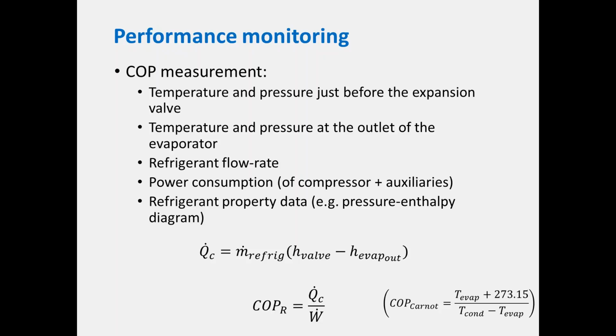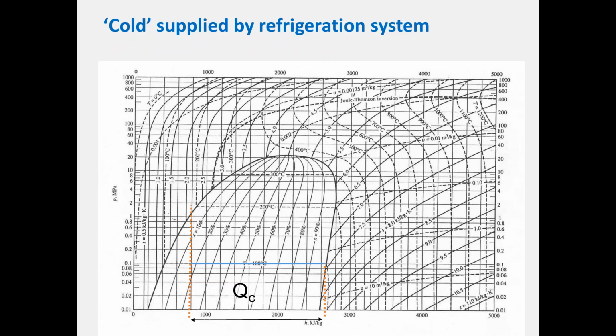If you then know the temperature and pressure at the outlet of the evaporator, perhaps the suction pressure if you've got that monitored, then if you are able to measure the flow rate of your refrigerant, if you can record the power consumption, maybe you've got a meter of the compressor plus auxiliaries, and if you get the right refrigerant property data, so if you know the refrigerant, then you can work it out from the refrigerant properties.